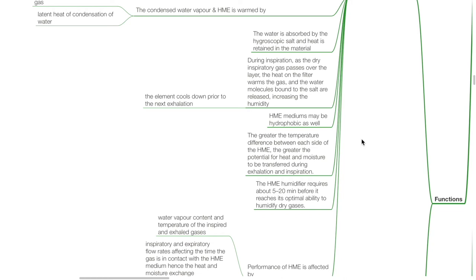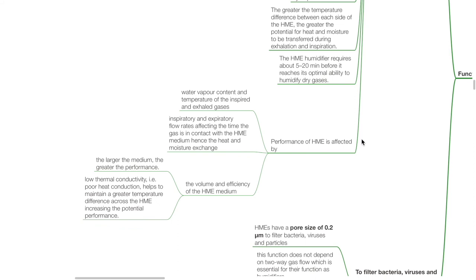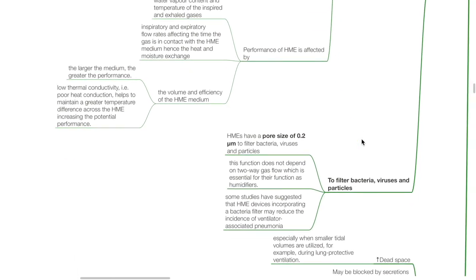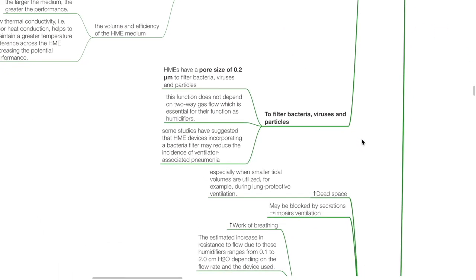The HME humidifier requires about 5 to 20 minutes before it reaches its optimal ability to humidify dry gases. Its performance is affected by the water vapor content and temperature of inspired and exhaled gases; inspiratory and expiratory flow rates affecting the time the gas is in contact with the HME medium; and the volume and efficiency of the HME medium — the larger the medium, the greater the performance. Low thermal conductivity helps maintain a greater temperature difference across the HME, increasing potential performance. Some studies have suggested that HME devices incorporating a bacterial filter may help reduce the incidence of ventilator-associated pneumonia.